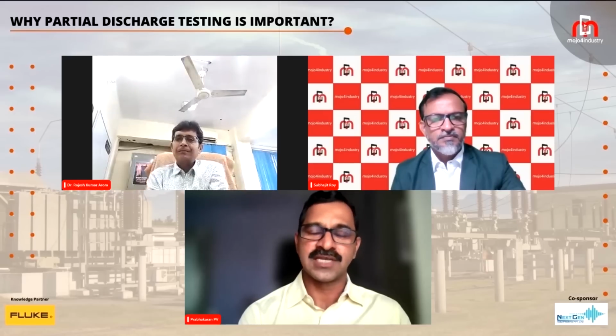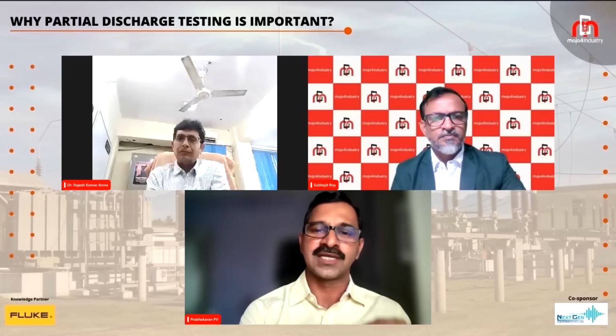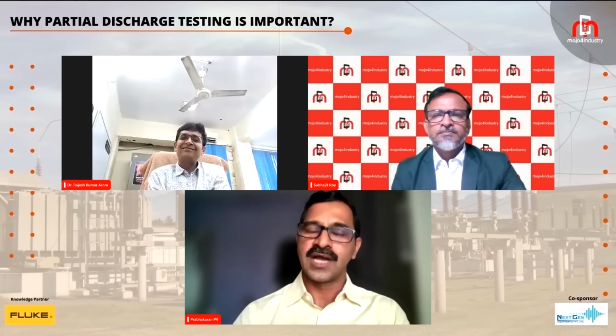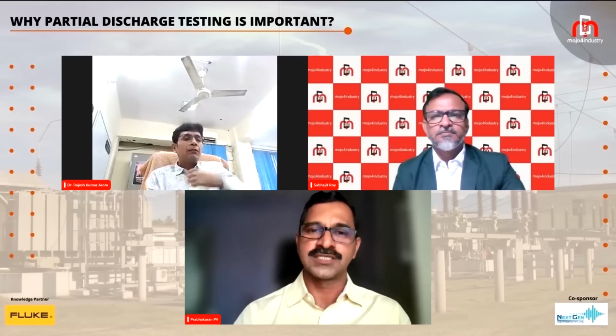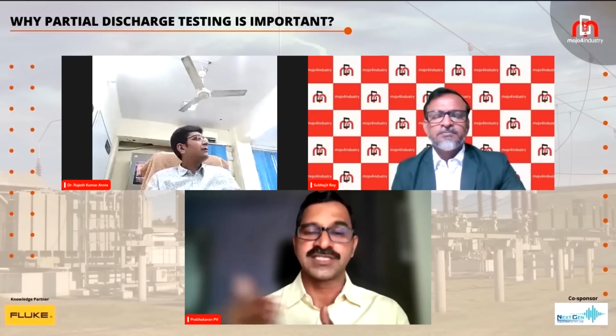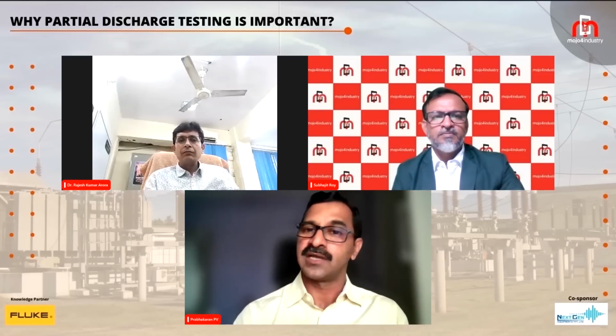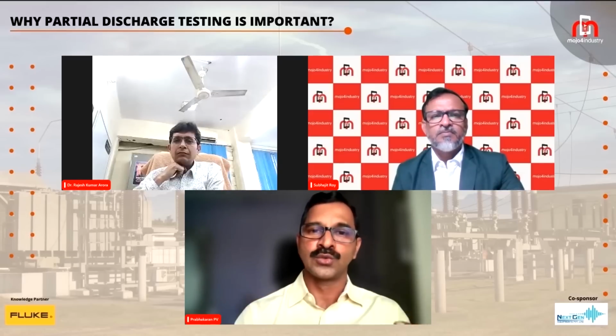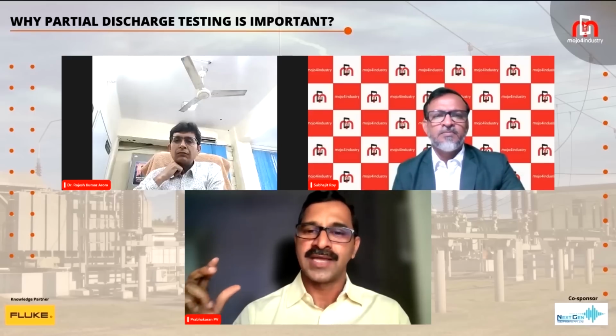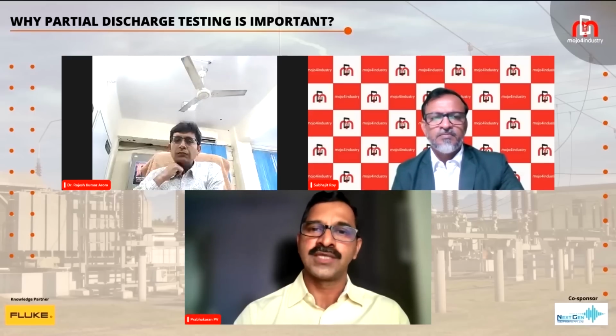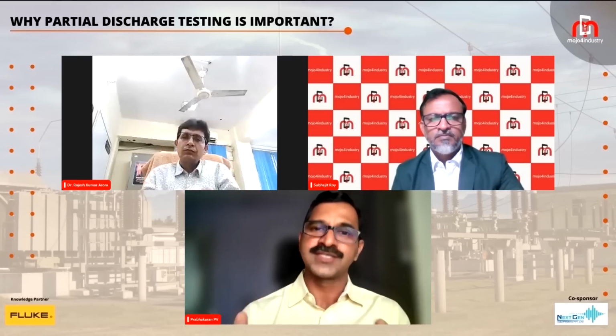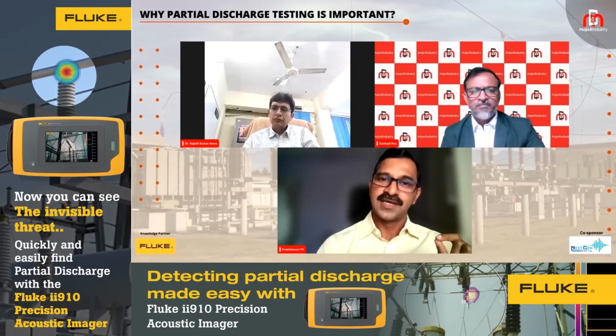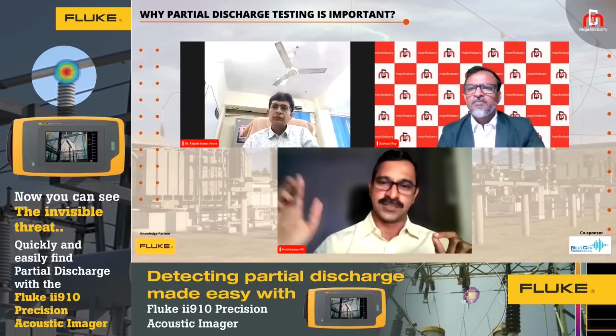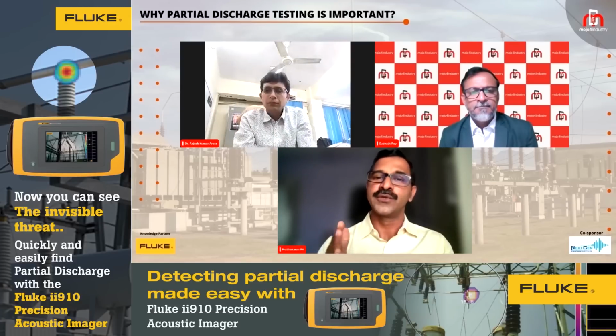For most electrical sensor-based measurement, you need to fix the sensor well before you charge the equipment. Acoustic systems can detect most partial discharge from a safer distance without touching the equipment. But can an acoustic sensor cover everything related to partial discharge? No. You have to choose the right equipment and analytical methods to identify the condition of these assets. Partial discharge always starts small and keeps growing, finally ending in a flashover. That's why you need to monitor it, document it, and have a precise mechanism to ensure unwanted shutdowns don't happen.